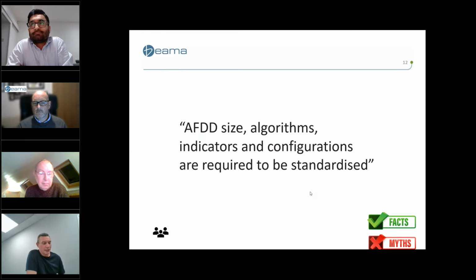Yeah, it's true to say at the moment that AFDDs coming from different brand manufacturers have slightly different philosophies in the way that they're communicating their information in the event of a fault. Certainly the AFDDs that I've seen and been used to so far, they're not just an AFDD. They do perform other functions as well. So the most common one is an AFDD as an integral part of an RCBO.